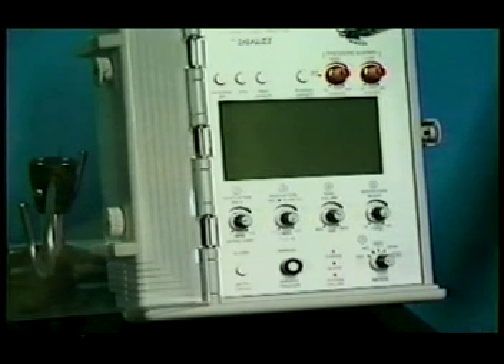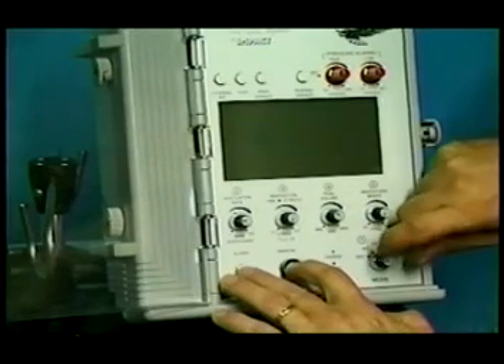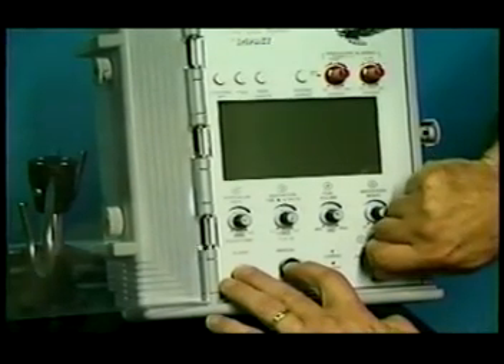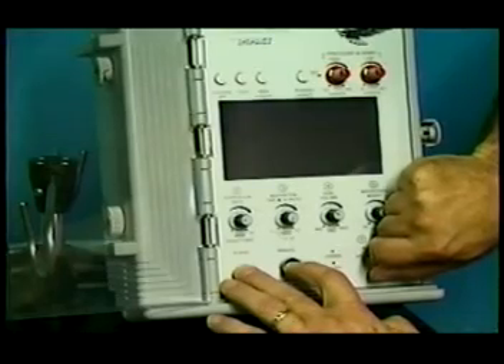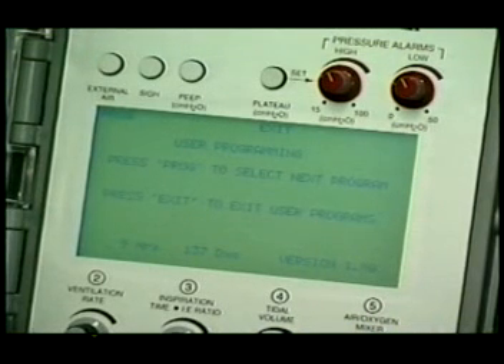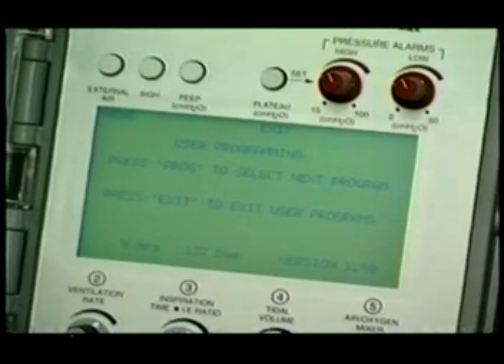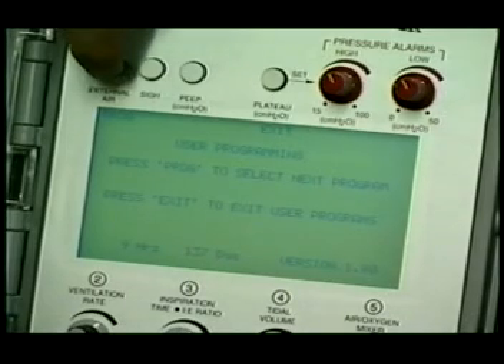To access this menu, simultaneously press the Alarm Mute Cancel push button and the Manual Breath Trigger push button while turning the Mode Select switch to any position except off. The LCD screen displays User Program's information and directions. The external air, sigh, PEEP, and pressure plateau push buttons have temporarily become soft keys, which are now used for decision-making in conjunction with directives appearing along the top line of the LCD. By pressing the push button above the word PROG, Program, we can scroll through each menu.